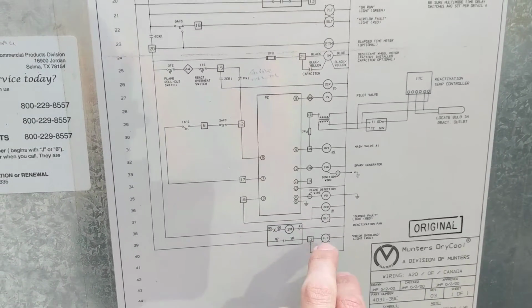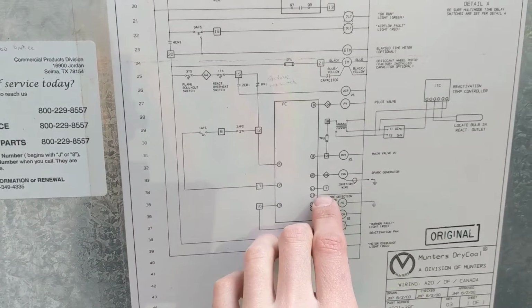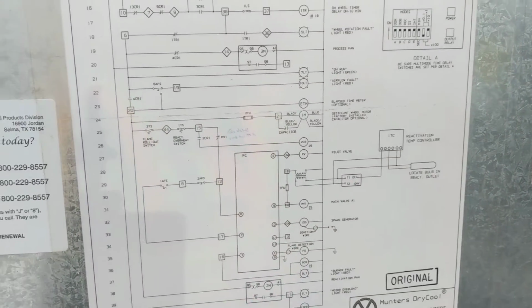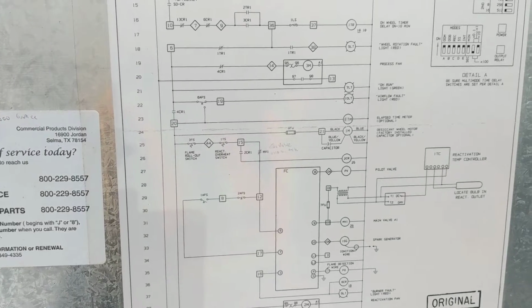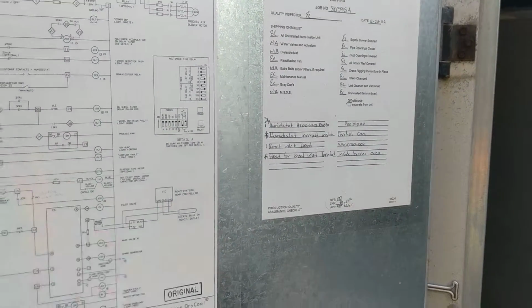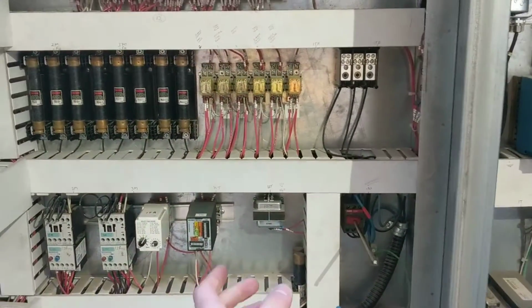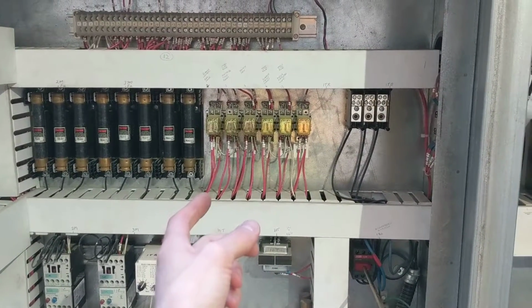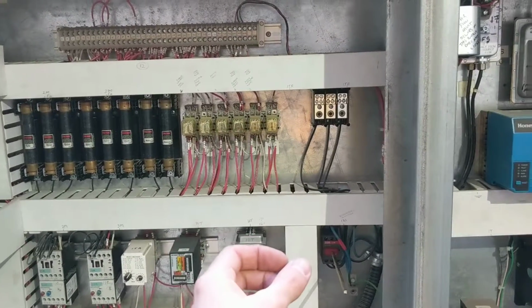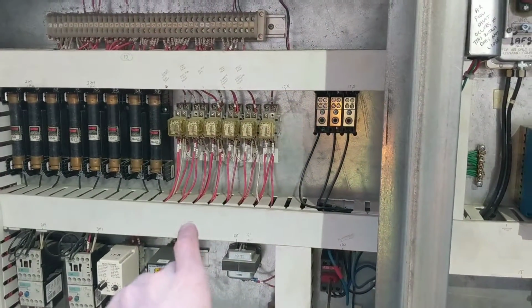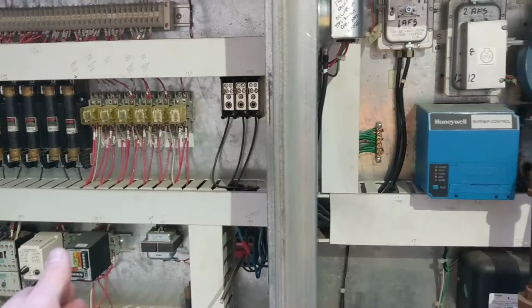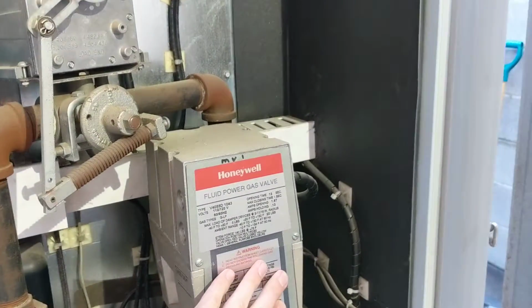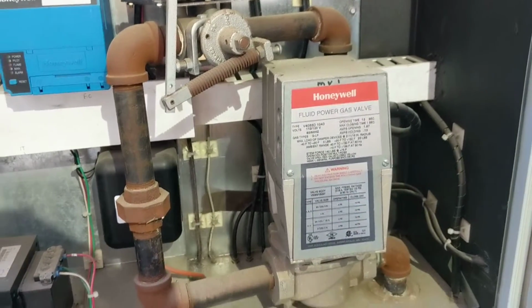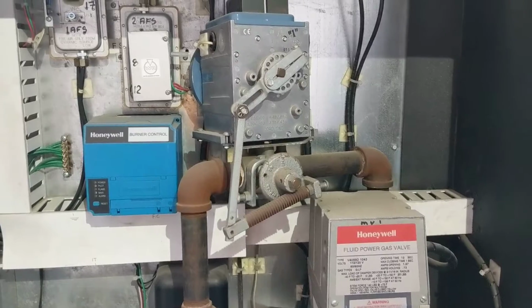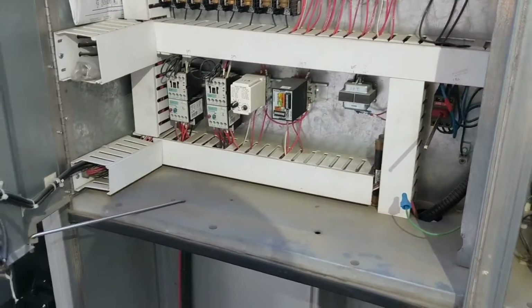So I don't know what's a good example here. A problem that was previously being troubleshot: we had an intermittent issue with the gas valve. By tracing where the power was getting dropped out using the wiring diagram, I had the power logger hooked up to the wiring that ran various things where the voltage was getting dropped. The power logger logged all the details and showed where it dropped out, and it turned out to be inside here. It was the little safety switch for the gas valve. So we replaced that, and that solved that problem.